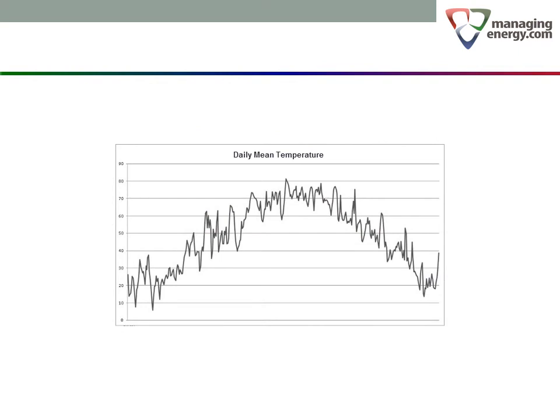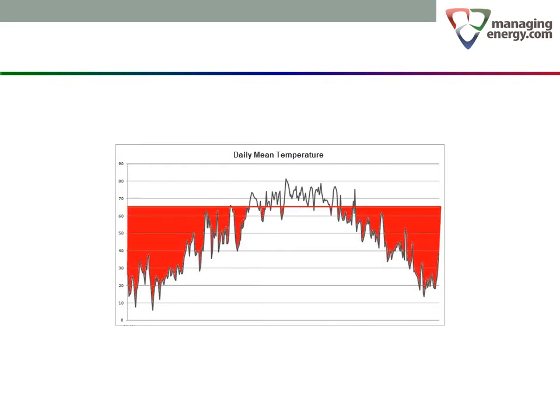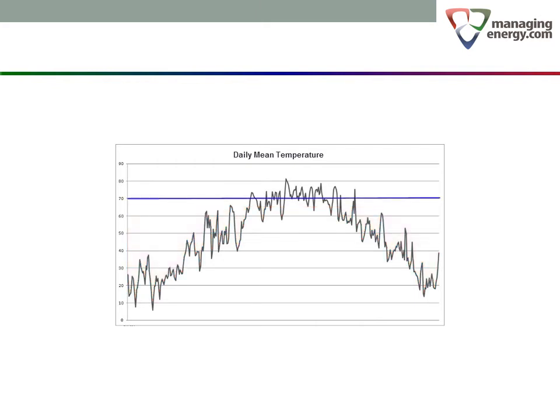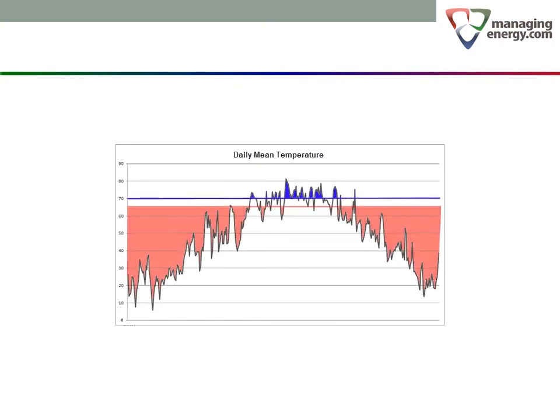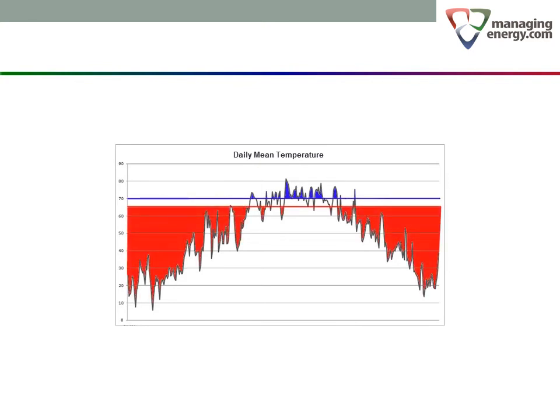Let's look now at the mean daily temperature profile for an entire year. The balance point temperatures dictate which days require heating and which days require cooling. If our heating balance point is 65 degrees Fahrenheit, any day with a mean temperature below 65 would require heat. The amount of heating for any particular day is dictated by the difference between the daily mean temperature and the heating balance point. Looking across the whole year, the area beneath the heating balance point shows the annual heating load, or in other words, the severity of the winter. If the cooling balance point is 70 Fahrenheit, any day warmer than 70 will require cooling. The area above the cooling balance point is the annual cooling load. In this example, the weather-sensitive energy use is dominated by heating, so it's a cooler climate. For most buildings, there is a temperature range between the two balance points when no heating or cooling is required.